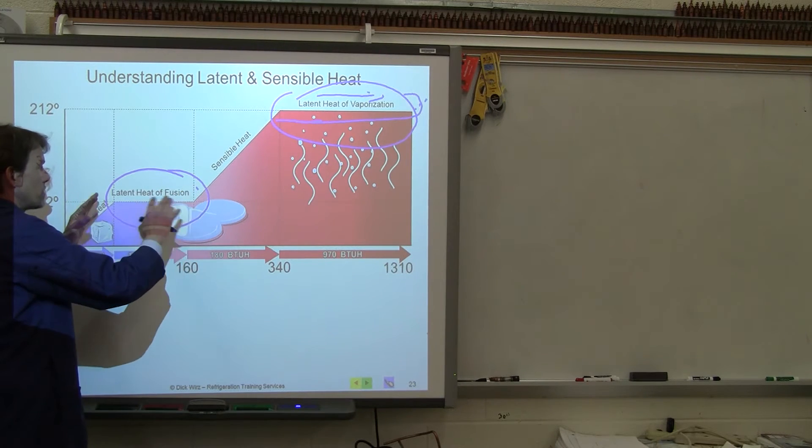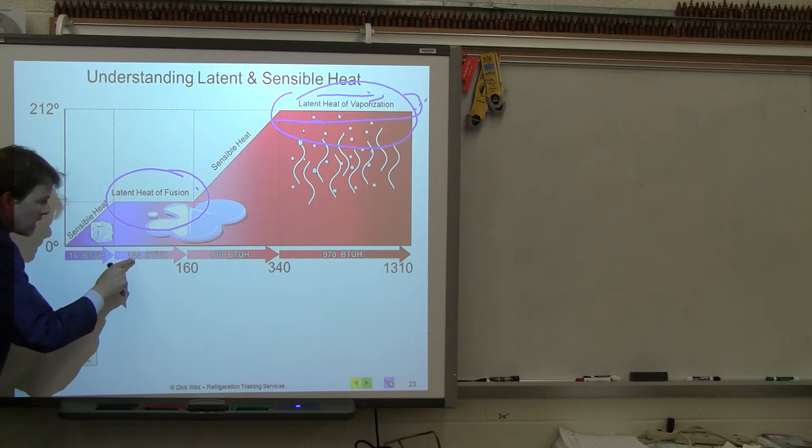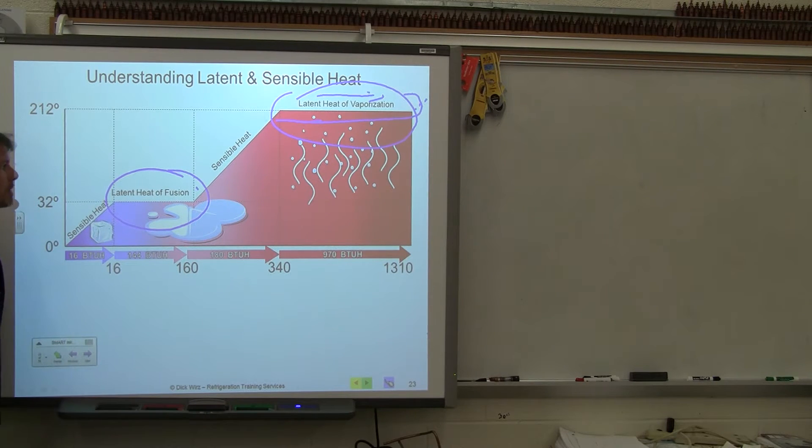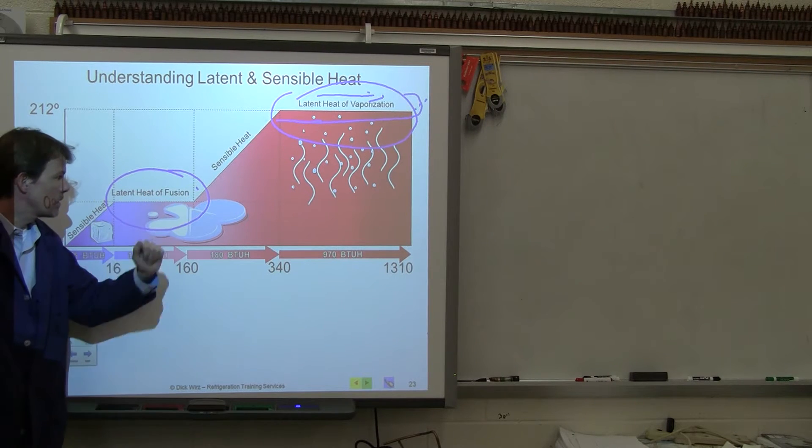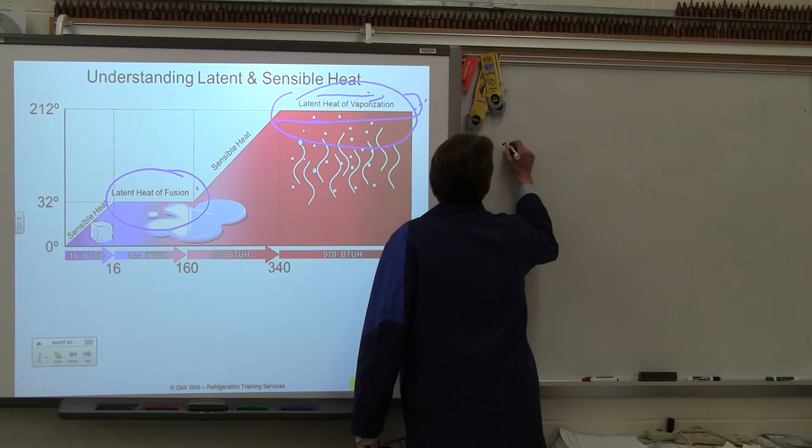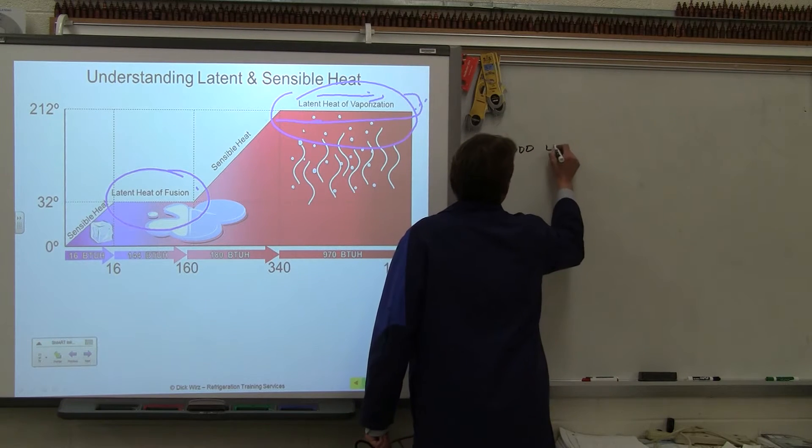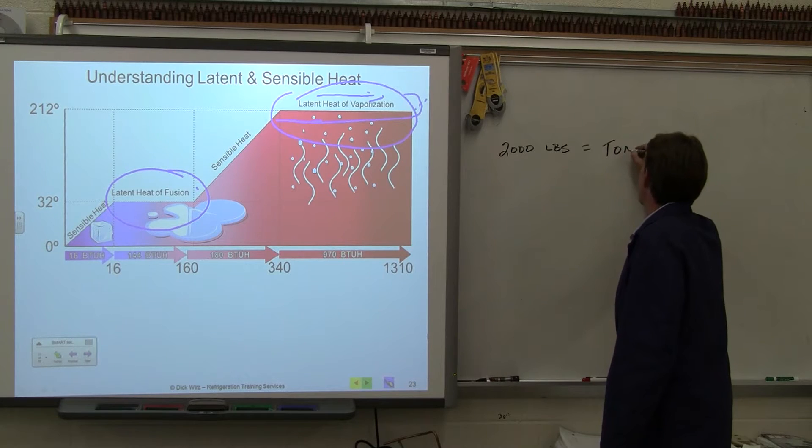All this is at sea level, standard pressure, standard conditions. At 32 degrees, it calculated it takes 144 BTUs worth of heat to melt a 1 pound block of ice from 32 degree solid to 32 degree liquid. In tonnage, we're normally dealing with, instead of 1 pound, we're dealing with 2,000 pounds of the substance, which is equal to a ton.